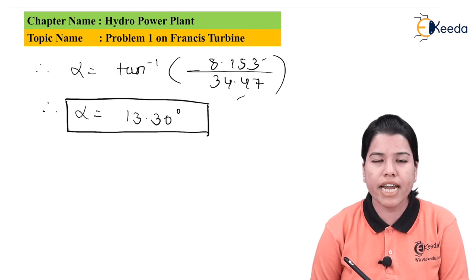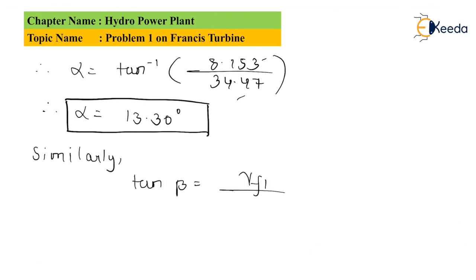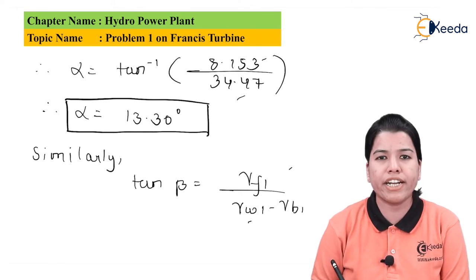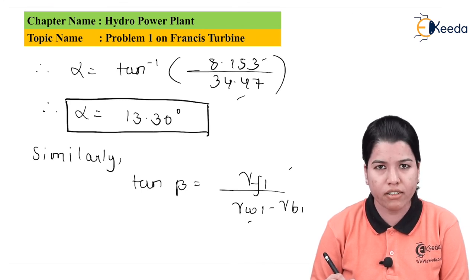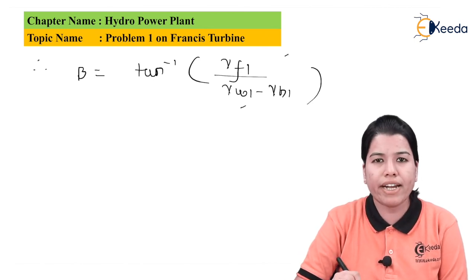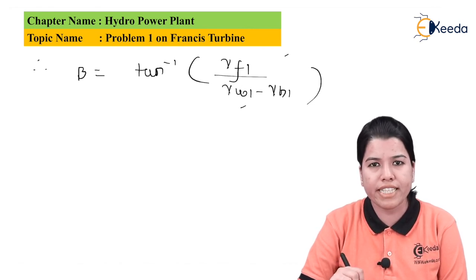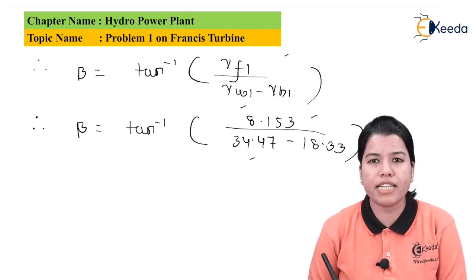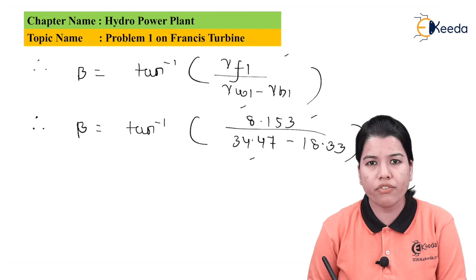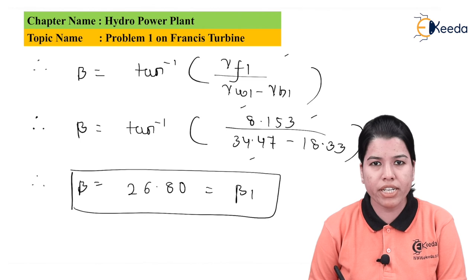The runner inlet vane angle beta1 is found using tan(β1) = Vf1 ÷ (VW1 − VB1). Therefore, β1 = tan⁻¹(8.153 ÷ (34.47 − 18.33)) = tan⁻¹(8.153 ÷ 16.14) = 26.80 degrees.